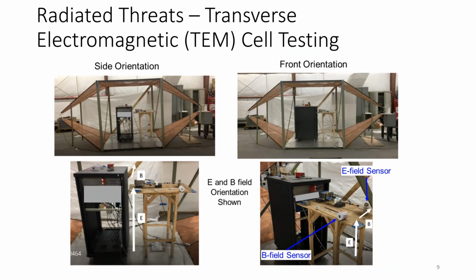The tests we do for the radiative threats are called the Transverse electromagnetic cell testing. So it's basically like putting your device in a microwave and seeing what happens to it. This is a really big microwave. You see the copper shielding around, that's the barrier of the device. And inside, the test object is placed. You can see it there in the black rack. And if you look closely at the close-up, there are some field detectors, and you can see the electric and magnetic fields are shown there.